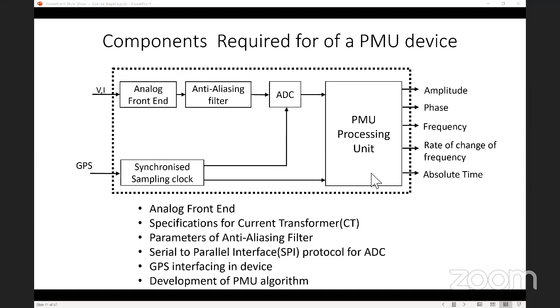For example, I have to do this for a current transformer. I may have a distribution transformer of this size, and I may want the maximum current to be less than 1000 amps. I may choose a CT which has only 5 amps - so a 1000 to 5 amp CT, depending on what I want to have.